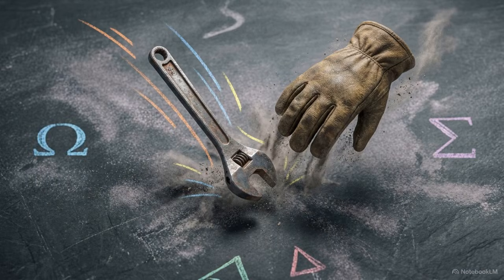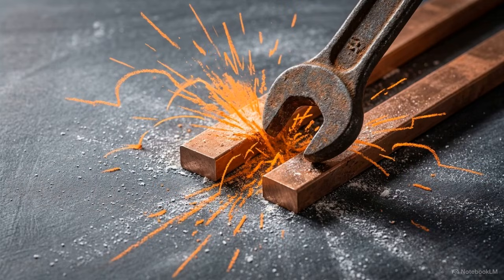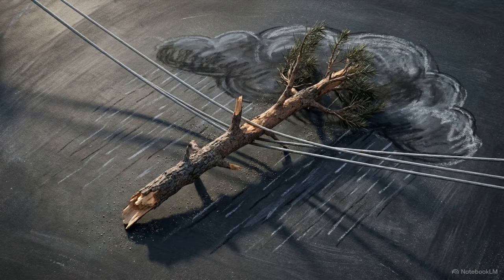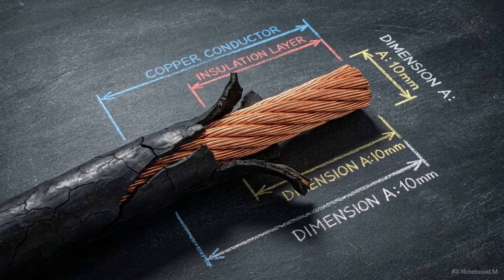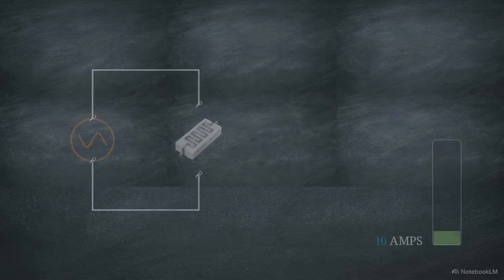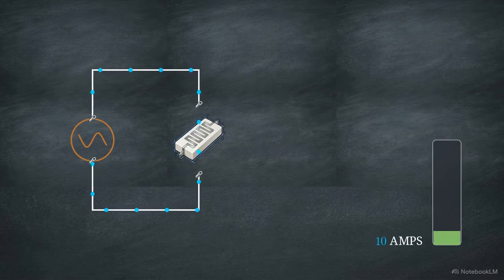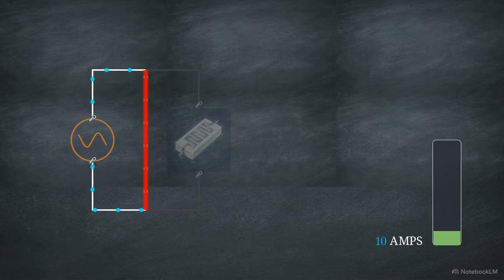That balance can be undone by something completely mundane: a dropped wrench across two bus bars, a falling tree hitting overhead lines, or old cable insulation wearing thin. When one of these triggers creates an accidental connection, it forms a new, nearly zero-resistance path for the electricity to travel. The current completely bypasses the system's intended impedance. This is the literal definition of a short circuit.